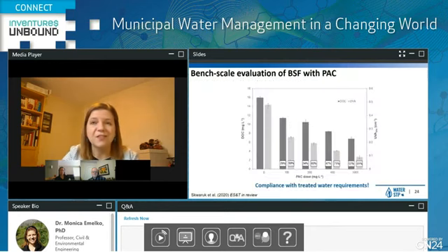So we adjusted. That's what treatment engineers do. And so we said, okay, let's go to the next level. And although enhanced coagulation is supposed to be a best available technology, we can explain why that didn't work as well. When we included the addition of powdered activated carbon with ballasted sand flocculation, we got to the point of being compliant with respect to treated water targets.